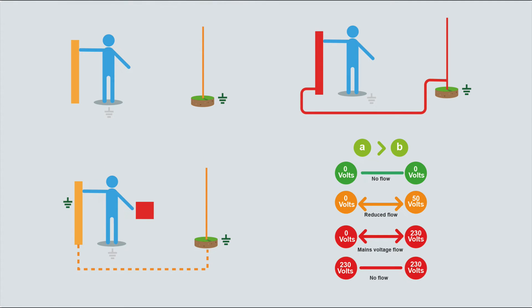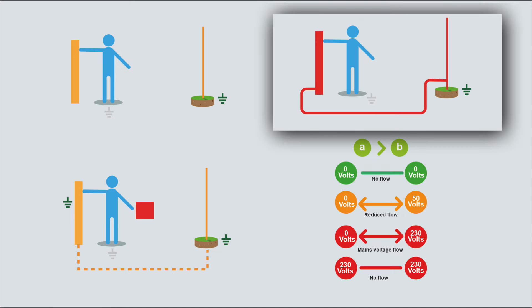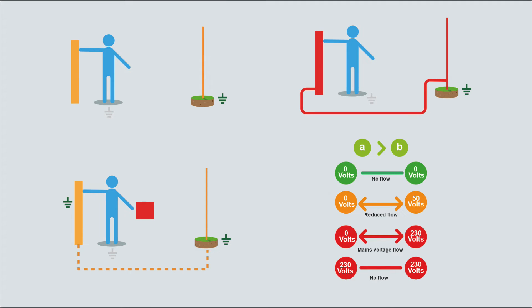As you can see here, we've got a person touching a piece of metal. Nearby there is an extraneous conductive part - it's got a good connection to the ground and it's introducing an earth potential. If for some reason that extraneous conductive part became live and we connected it to that piece of metal, that piece of metal will then become live as well. Was there any need to connect that piece of metal to the extraneous conductive part? As you can see, if that connection wasn't there, that piece of metal wouldn't rise to a potential, wouldn't become live. So you've got to be careful that you don't just bond everything in sight - any piece of metalwork - because it might not need to be bonded. If it's just a piece of metal sitting there that can't introduce a potential, leave it alone, because bonding it could actually under fault conditions make that piece of metal come live.